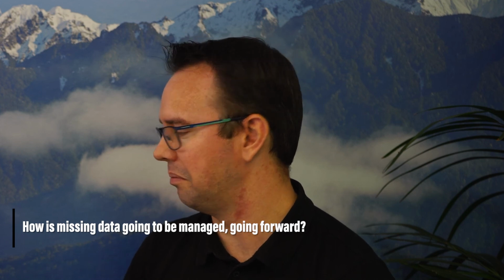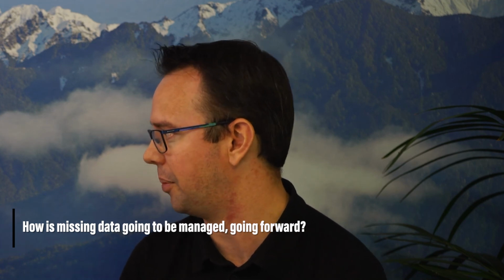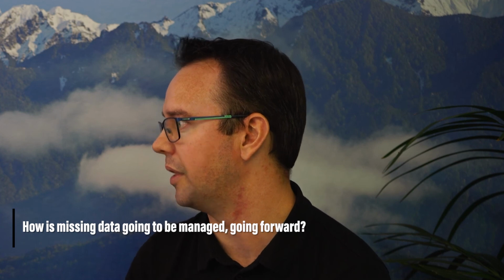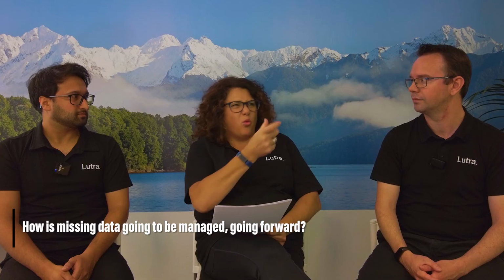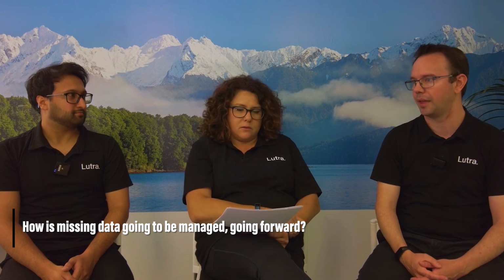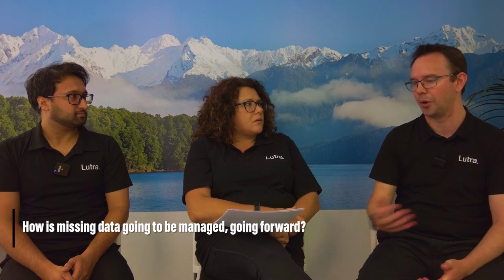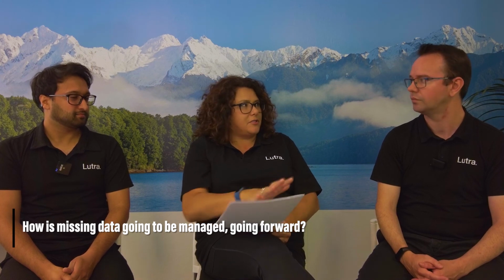Where do those numbers come from? Well, it basically relates to the 15-minute events that we've talked about before, and the 5% of the day. So if you're missing enough data to hide one of those events, then it might have been non-compliant. You don't know, so therefore that's a technical non-compliance. So it's 15 minutes in a block, or 72 in total over the day. That means missing data may become more of a problem for a supplier. Now this has been clarified, but in principle, it's a definite improvement. Yeah, great. So again, good to get the clarity around it.